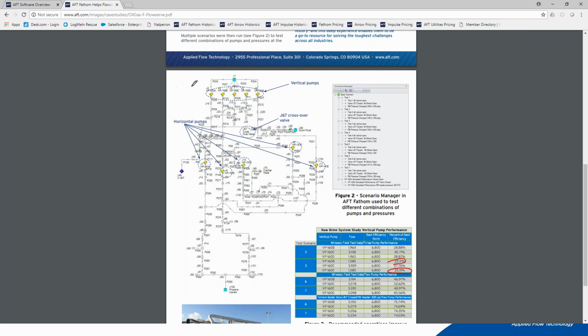Well, here is the problem. Essentially, these 5 pumps, when several of them were operating together at the same time, usually they had 3 operating at the same time, they would fight each other. And so when they fight each other, they struggle to find their own operating point on their pump curves. And eventually, you have pumps that are just supplying way, way, way less flow than what they need to actually be supplying.